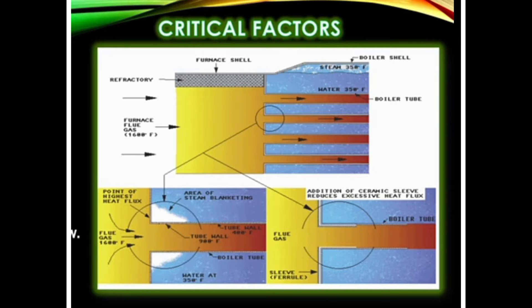In the above picture, everything is normal: flue gases are coming, water is inside the tubes, and steam is generating at 350 degrees in the boiler drum. Now, looking at the picture below, you can see that when flue gases enter, just before the tubes there are corners and edges where the heat flux is very high.